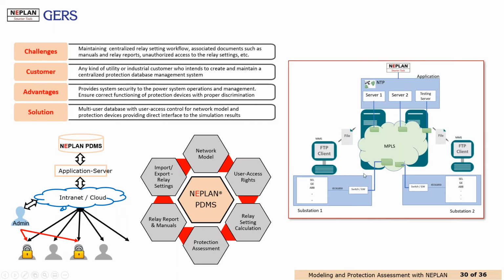And we can see how, using communication protocols like IEC 61850 or FTP, we can send through to the application servers, maybe a SCADA server, maybe a server for the protection assessments, or maybe a server for the protection management systems. We can connect the NEPLAN web services to any application in this server. And for sure, one of them could be for getting automatic settings or could be for the protection assessment in order to validate the existing settings on the network.